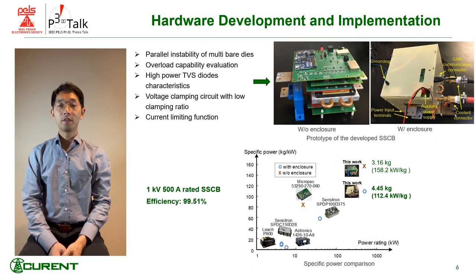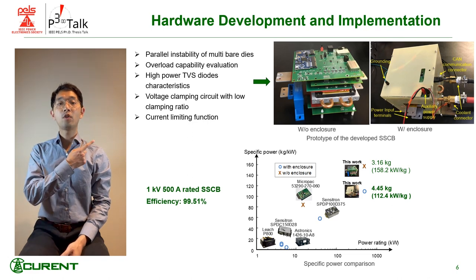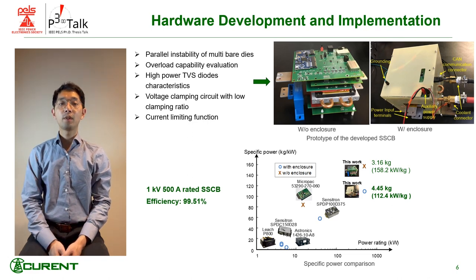Beyond the parallel instability issue, I also studied overload capability evaluation, high-power TVS diode characteristics, voltage clamping circuit with low clamping ratio, and the current limiting function. Combining all these, I was able to build a 1kV 500A rated SSCB prototype.